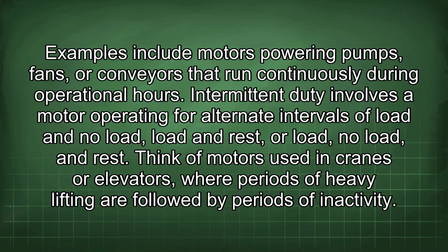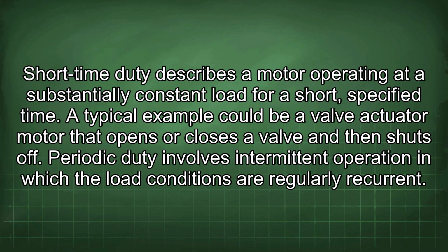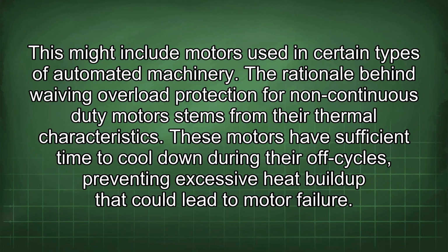of inactivity. Short-time duty describes a motor operating at a substantially constant load for a short, specified time. A typical example could be a valve actuator motor that opens or closes a valve and then shuts off. Periodic duty involves intermittent operation in which the load conditions are regularly recurrent. This might include motors used in certain types of automated machinery.